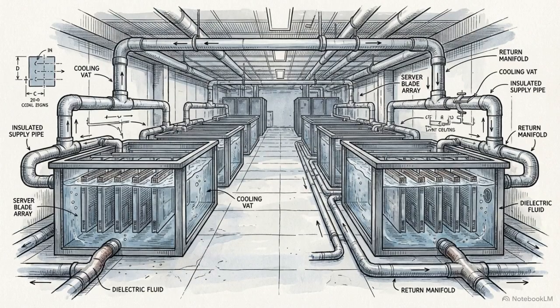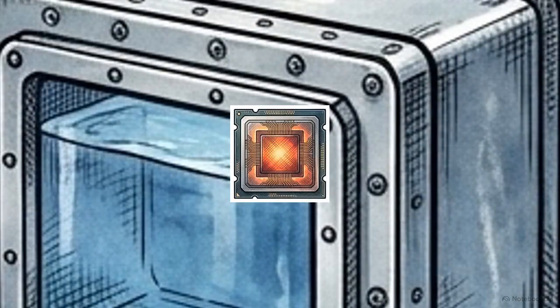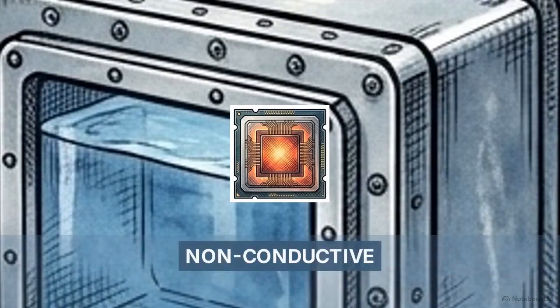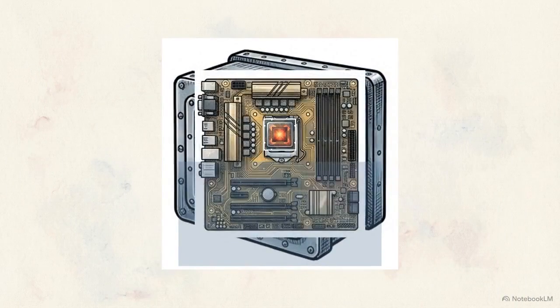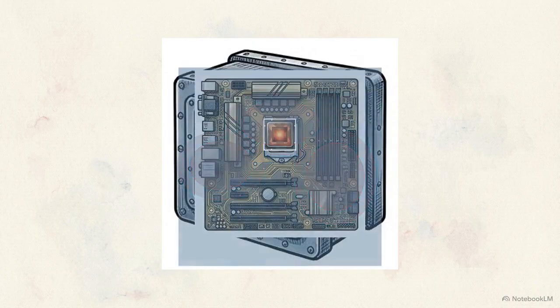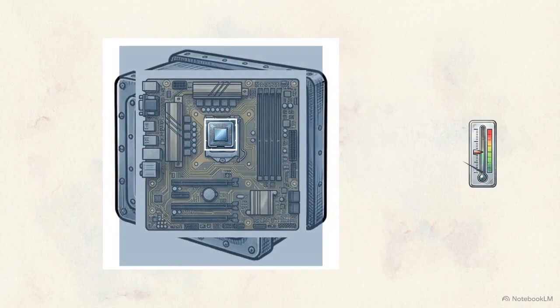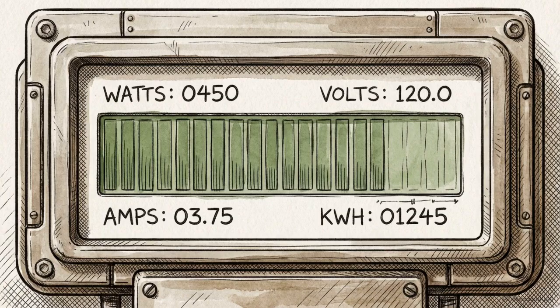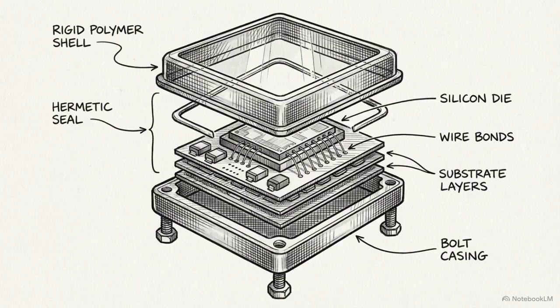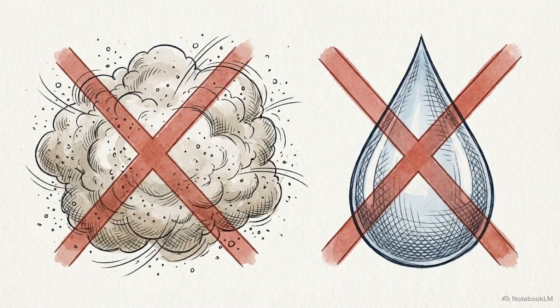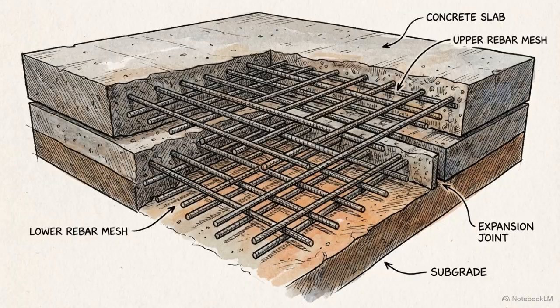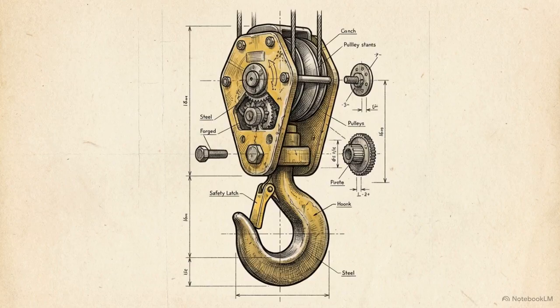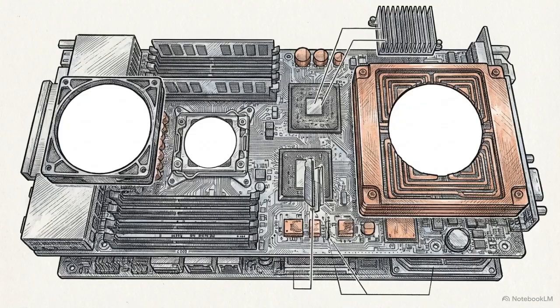The next step up is single-phase immersion. This takes vertically oriented, fanless servers and submerges them completely into tanks of non-conductive dielectric fluid. Dielectric fluid is a highly specialized engineered coolant that safely touches active electronics without causing a short circuit. Because 100% of the hardware makes direct contact with the coolant, thermal hotspots are entirely eliminated. This pushes limits to 80 kilowatts, while permanently isolating the sensitive components from environmental dust and humidity. The facility trade-offs are heavy. You need drastically reinforced floors, specialized overhead hoists for maintenance, and heavily modified server hardware.